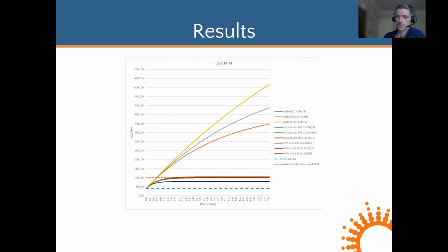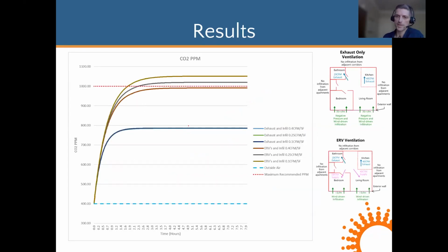Only with ventilation are we able to curb that and bring it down to an acceptable level down here with the ERVs and exhaust-only scenario. So zooming into those, we can see that with ventilation, the CO2 levels level out. For the exhaust only scenarios, we have 3 scenarios with the varying infiltration rates, and they're about the same, so it looks like one line here. They leveled out at about 780 parts per million in around an hour. And then with ERV units, they leveled out right at around our threshold of 1,000 parts per million in about 2 hours. And the difference between these levels here is based on our design.